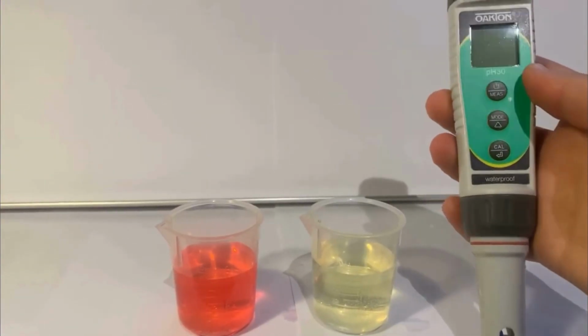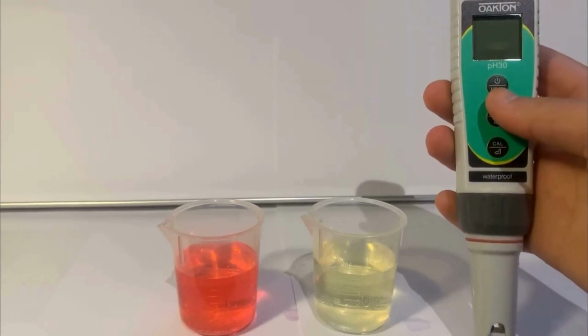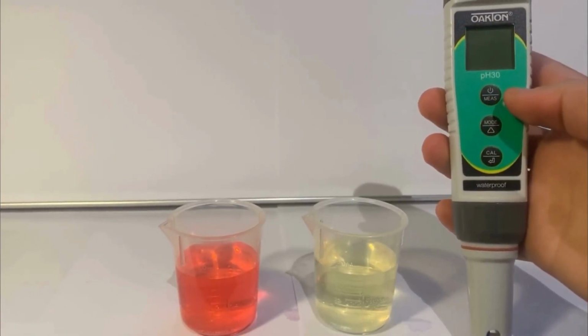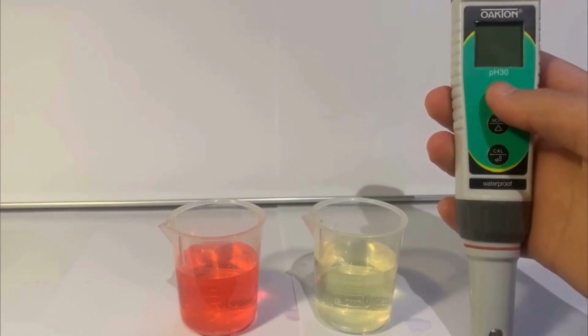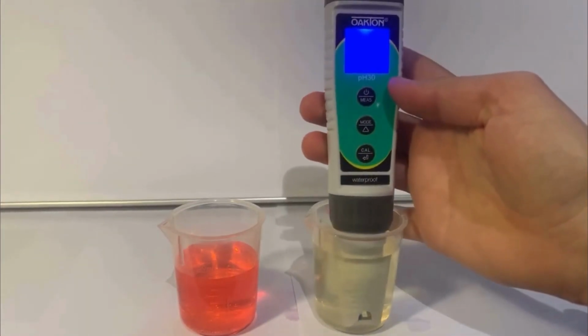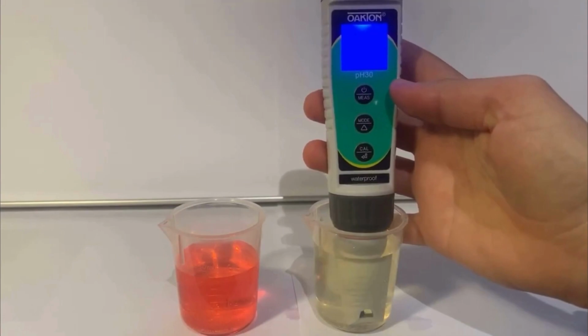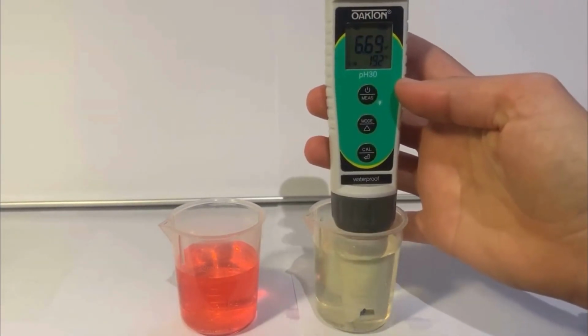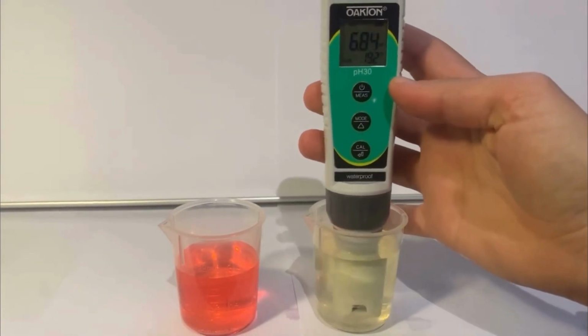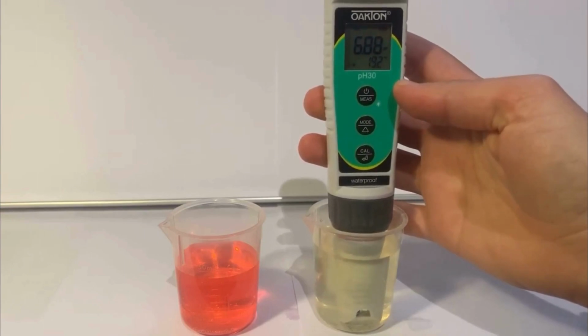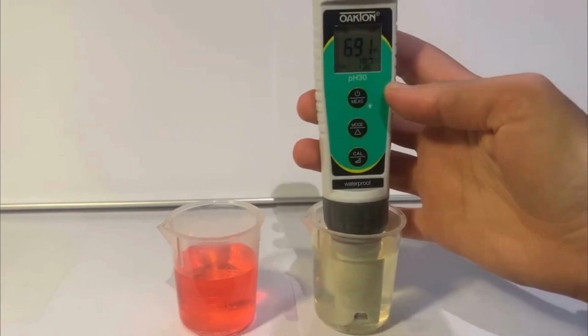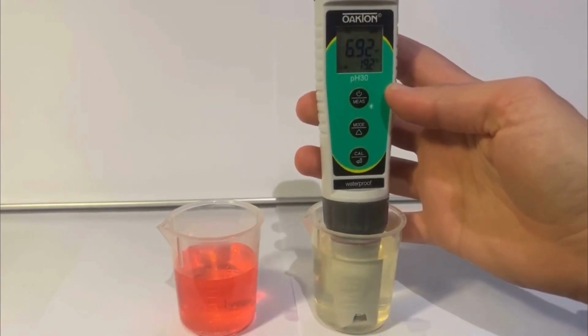When you return from the field, we want to ensure that no probe drift has occurred. So we'll check this by taking measurements of our calibration solutions. Turn on your meter and place it into buffer 7 solution. We are not entering calibrations here, just taking a reading. Allow the stabilization icon to appear, then record your temperature and pH reading on your datasheet.